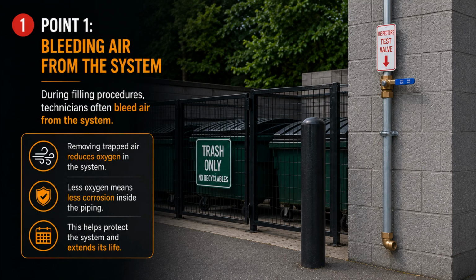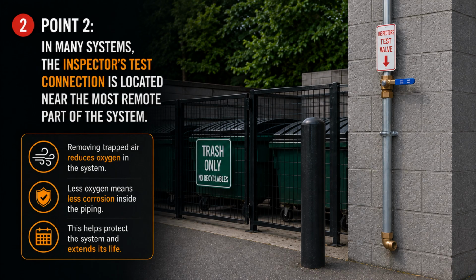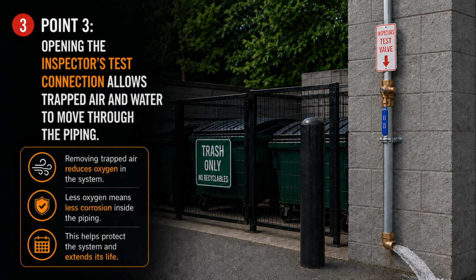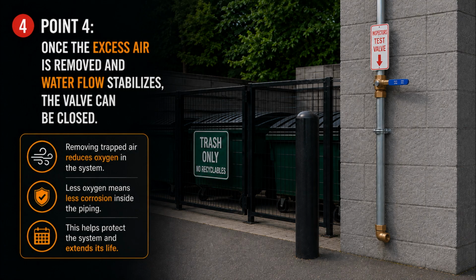One of the biggest goals is reducing trapped oxygen. Oxygen can accelerate corrosion. During filling procedures, technicians often bleed air from the system. In many systems, the inspector's test connection is located near the most remote part of the system. Opening the inspector's test connection allows trapped air and water to move through the piping. Once the excess air is removed and water flow stabilizes, the valve can be closed.